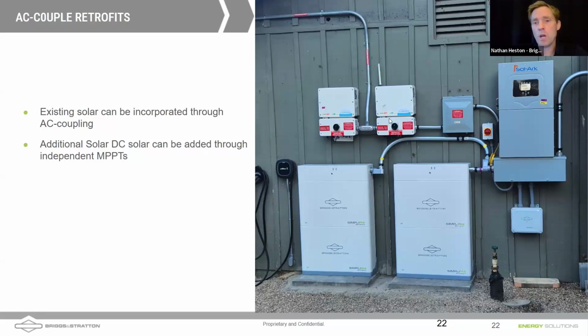So you can see here on the screen, we've got a couple of SolarEdge inverters, probably had a rooftop solar array that they didn't want to get back on the roof and rewire. And so we're AC coupling these two inverters, probably two 20 amp inverters, right, into the SolArk through the generator port. And now if the grid goes down, they do have this solar power. This solar power is kept alive by the SolArk inverter. We also have batteries to back up their loads. And so in a grid down situation, this system has backup power. And so some advantages to doing it. This is called the AC coupling of string inverters.